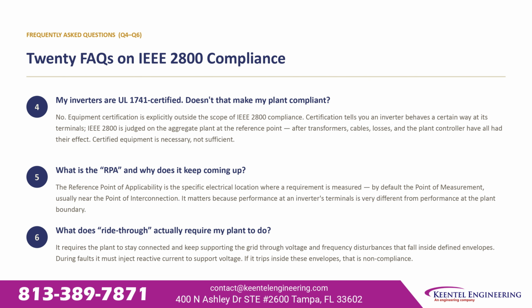Your inverters are UL 1741 certified. Doesn't that make your plant compliant? No. Equipment certification is explicitly outside the scope of IEEE 2800 compliance. Certification tells you an inverter behaves a certain way at its terminals. IEEE 2800 is judged on the aggregate plant at the reference point. After transformers, cables, losses, and the plant controller have all had their effect, certified equipment is necessary, but it isn't sufficient on its own.